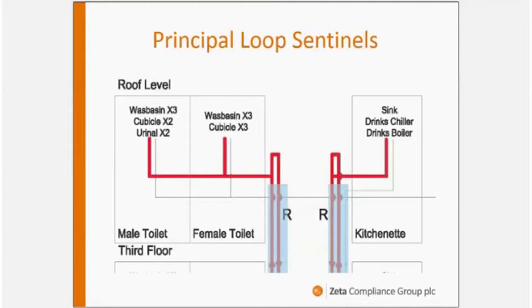We've looked at water systems over the years and fussed over 1 or 2 or 3 pipe diameters, and all the time, in the panels, in the service voids and risers in our buildings, we've got return legs. It's effectively static. Dead legs could be tens of meters in length. And that's why this new sentinel point is defined on the return leg.